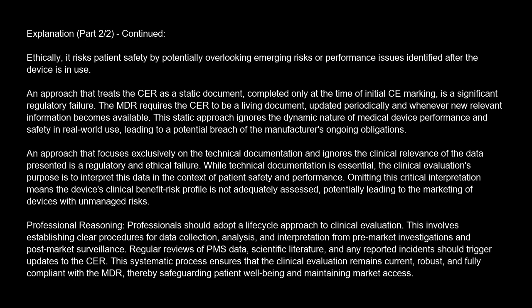Professional reasoning. Professionals should adopt a life-cycle approach to clinical evaluation. This involves establishing clear procedures for data collection, analysis, and interpretation from pre-market investigations and post-market surveillance. Regular reviews of PMS data, scientific literature, and any reported incidents should trigger updates to the CER. This systematic process ensures that the clinical evaluation remains current, robust, and fully compliant with the MDR, thereby safeguarding patient well-being and maintaining market access.